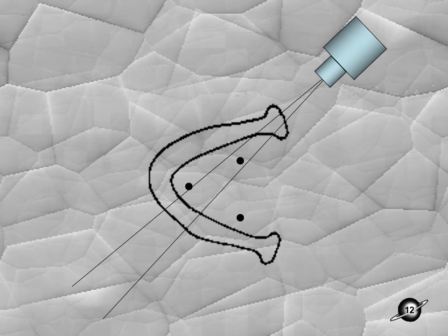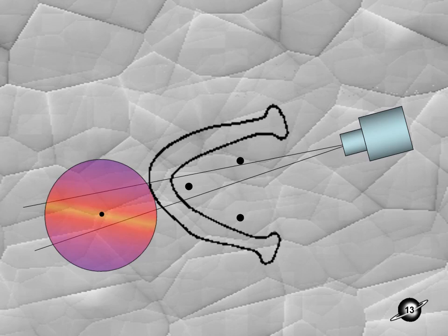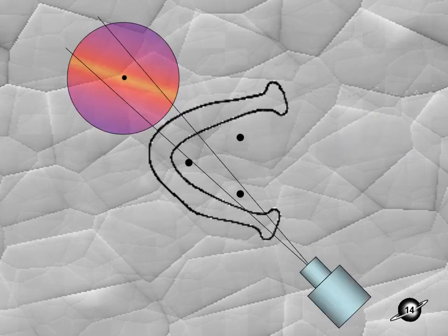I hope you guys are following. The patient is positioned in a gantry in an X-ray machine. His mandible is not moved. What is moving here is the X-ray source, which is rotating around the mandible, and we have a disc here. This is an X-ray film. So the X-ray source and X-ray film are rotating, but both are rotating in opposite directions. The X-ray beam is passing through the center of rotation, and this particular area of the mandible is superimposed on it.